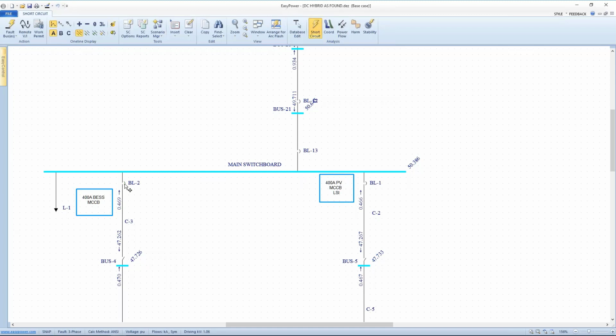For starters, we're going to open these breakers and try this again and look at the incident energy. At that point, we're getting at least civil levels, less than 4 calories on the main switchboard. So that brings up a problem: how do we resolve what's going on? Clearly there's something amiss downstream from one of these legs.